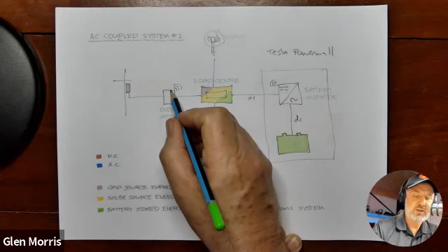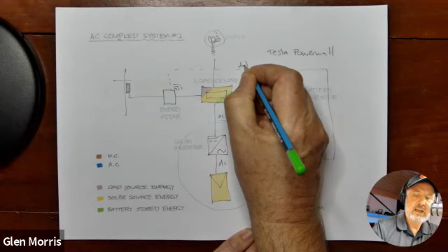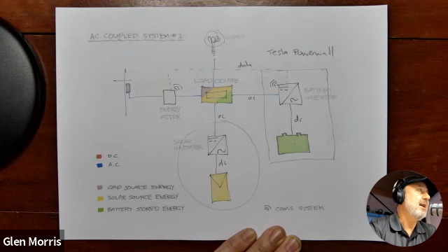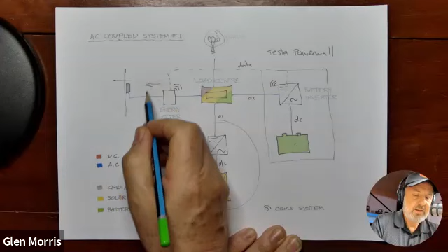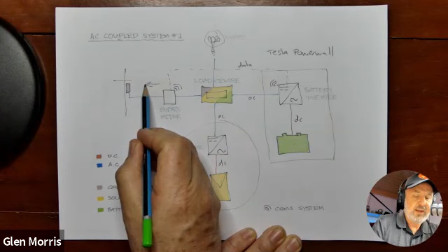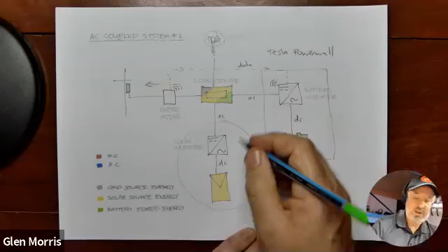So you'll notice I've just done a little Wi-Fi symbol here, but in practice, that'll be a data cable connecting the two together. And so that data cable will allow the battery inverter to see which way energy is flowing. Is it flowing towards the grid like this, or is it flowing from the grid back to the loads? Now, if it can see energy flowing out, it communicates that along this data cable, and so the battery inverter suddenly sees an opportunity to capture surplus solar energy.